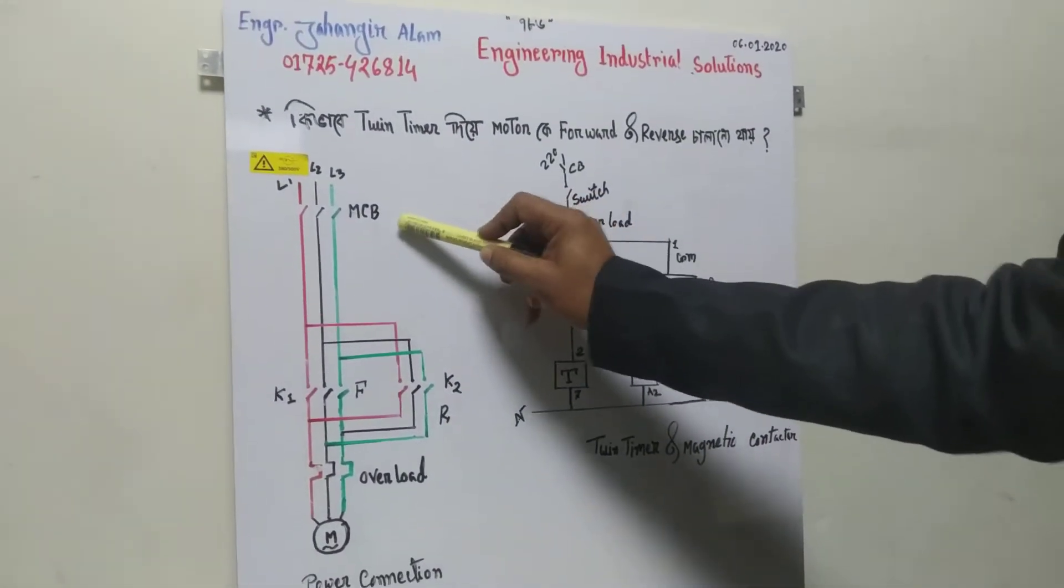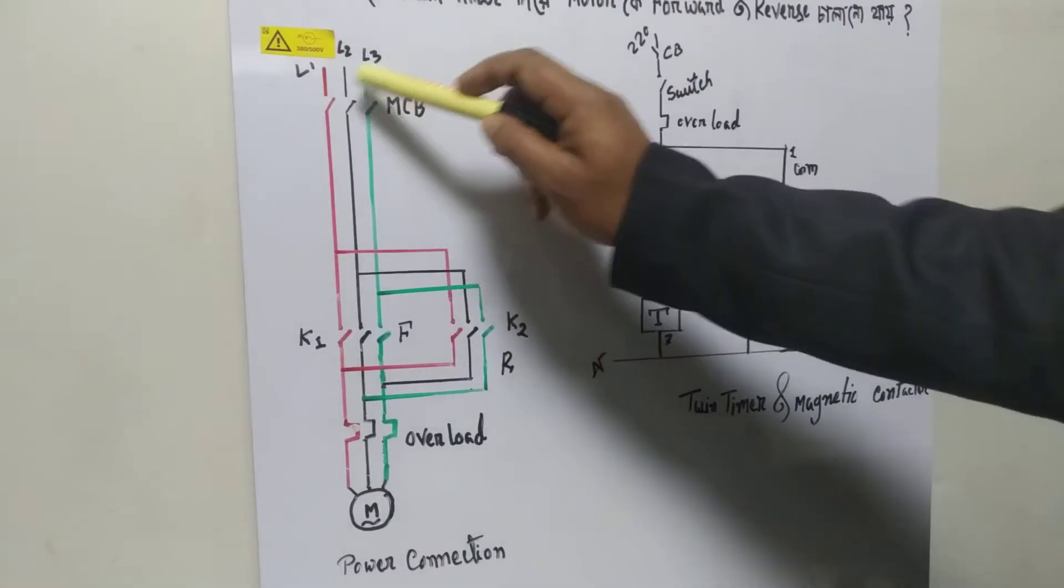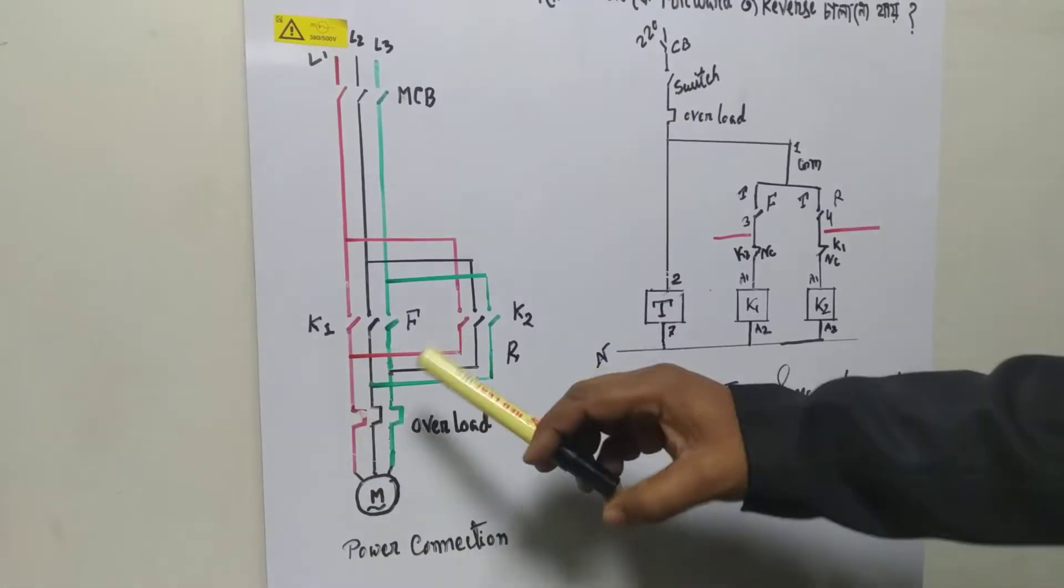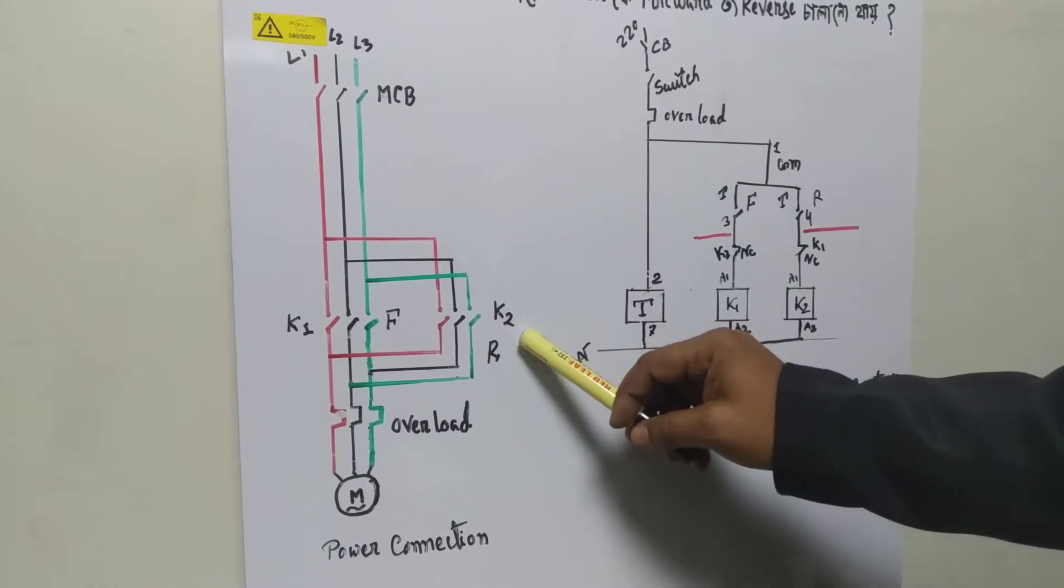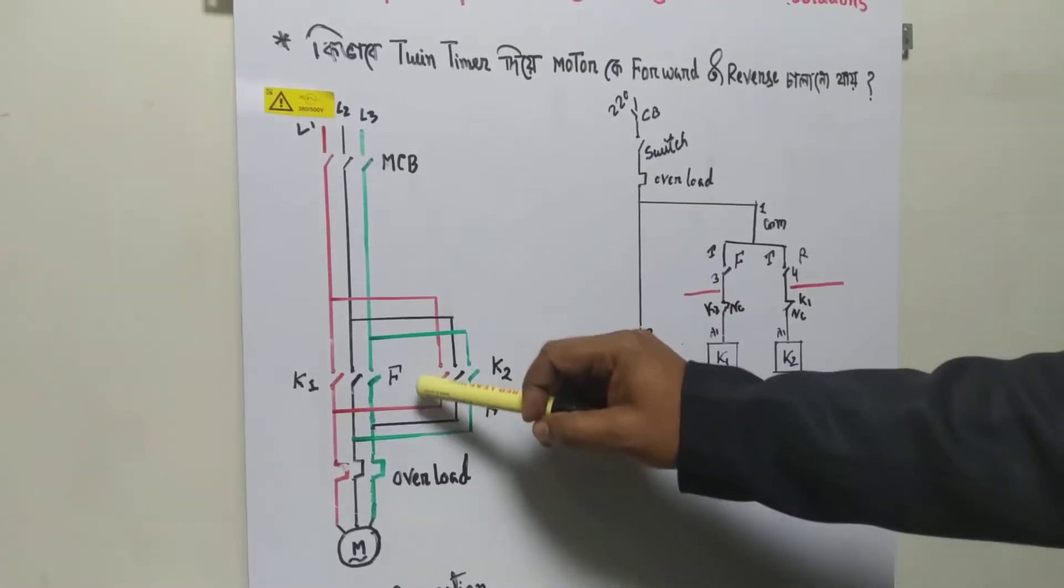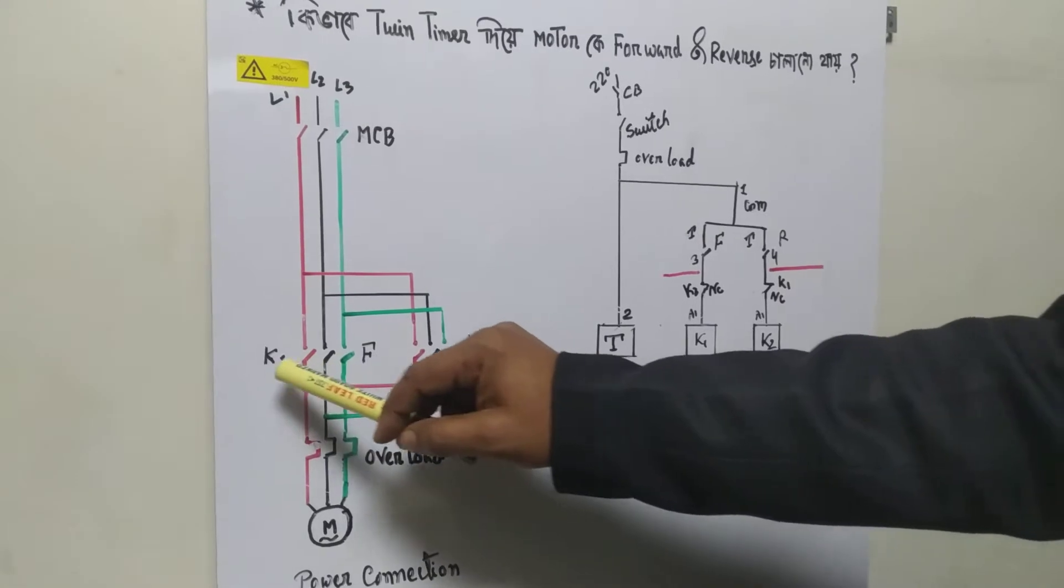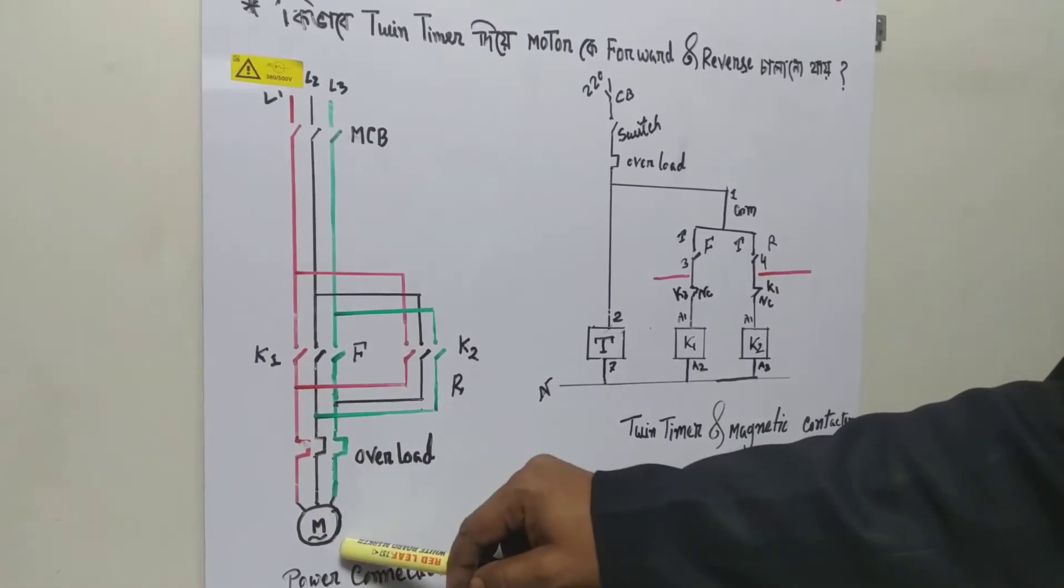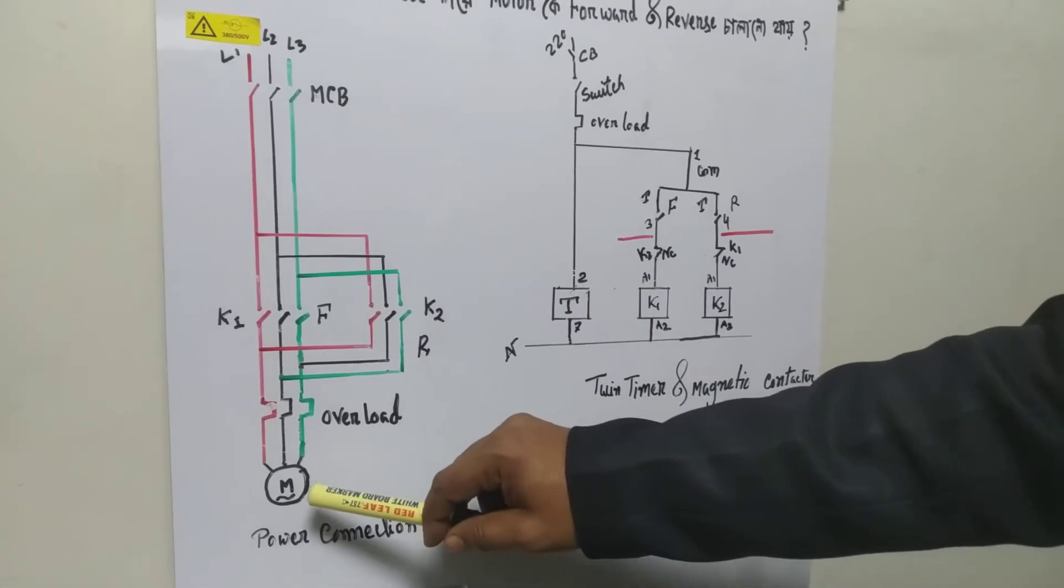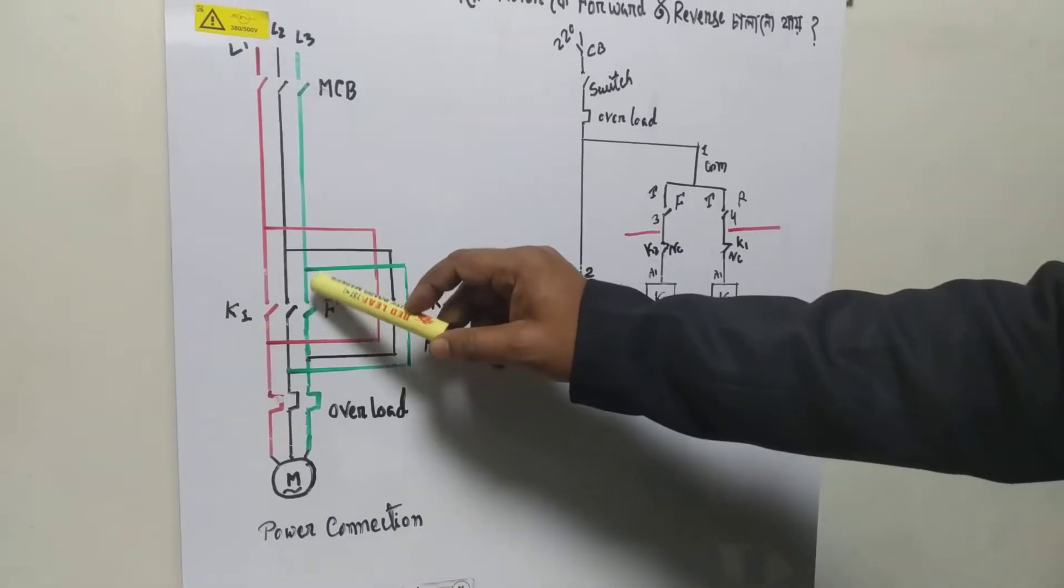First, let's look at the power connection input line. We have L1, L2, L3 connected to the magnetic contactor for forward and reverse. There's also an overload protection and the motor. When K1 magnetic contactor activates, the motor runs forward. When K2 activates, the motor runs in reverse.